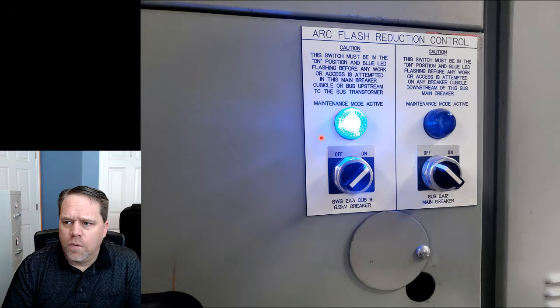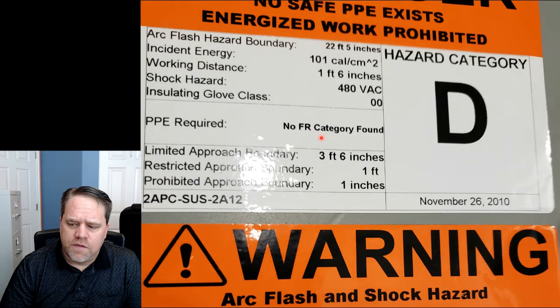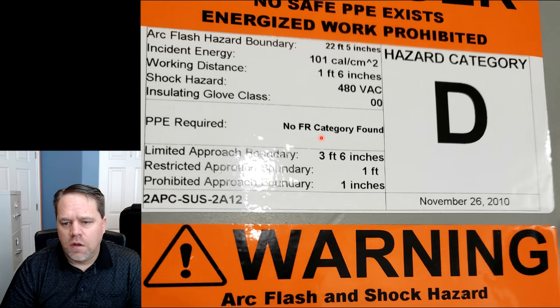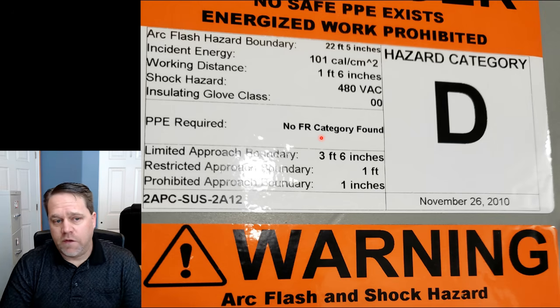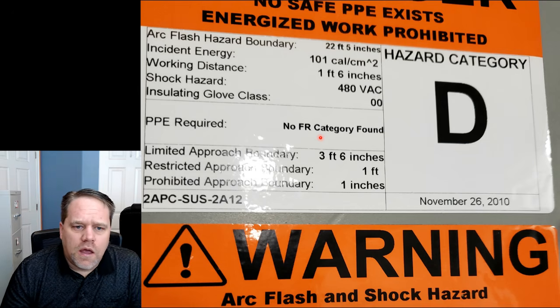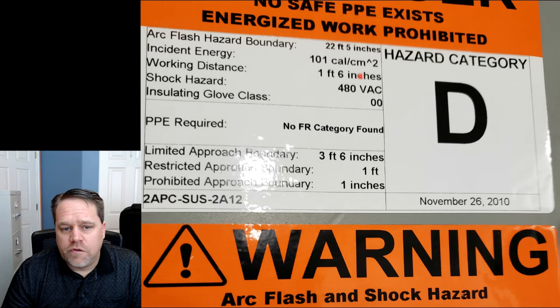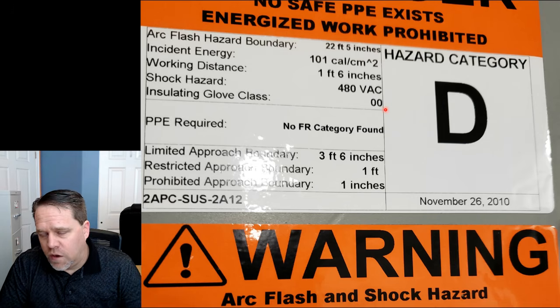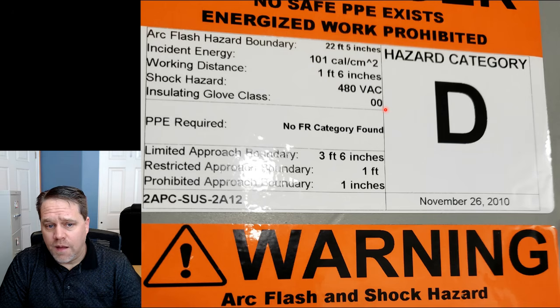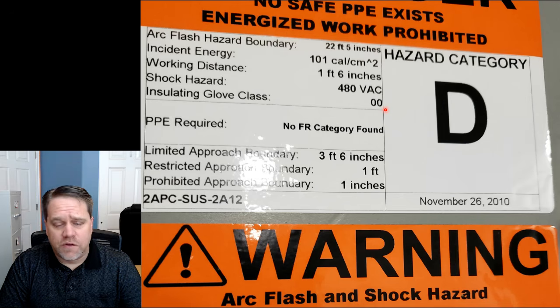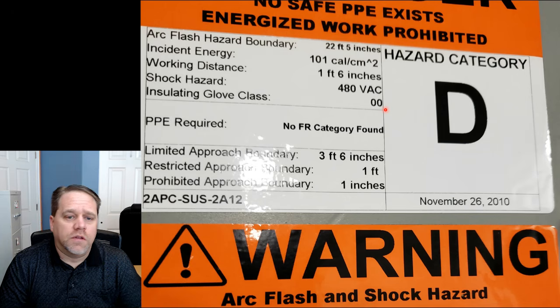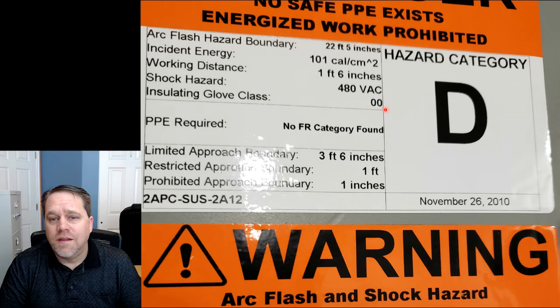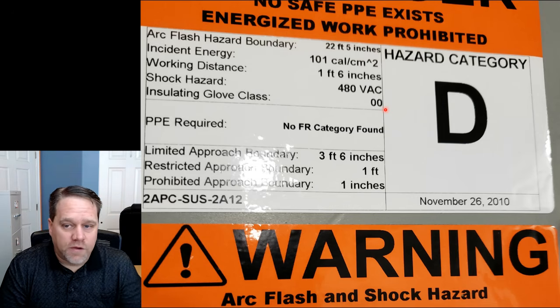Now, what do you do if you're working on an energized piece of equipment that will kill you if it blows up, regardless of your personal protective equipment? Take a look at this warning label. If I'm in front of this piece of equipment, which is only 480 volts, and something goes wrong causing an arc flash, we have an incident energy of 101 calories per square centimeter. If you're not familiar with what that means, that's a closed casket funeral, unfortunately. There's no personal protective equipment in the world that will save you from a 100 calorie incident — the shock wave from the event will kill you.